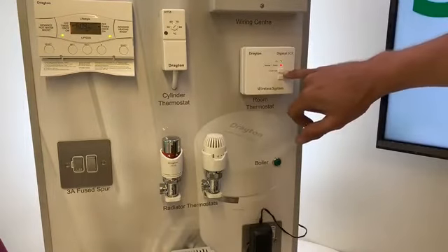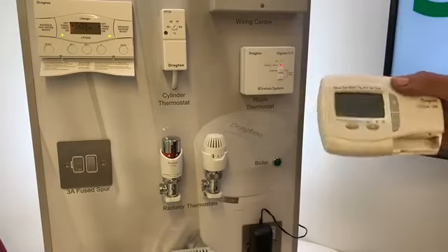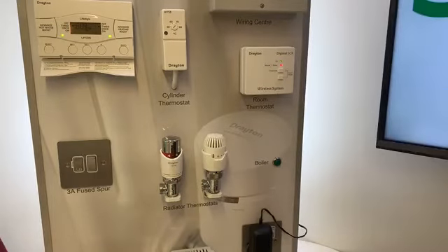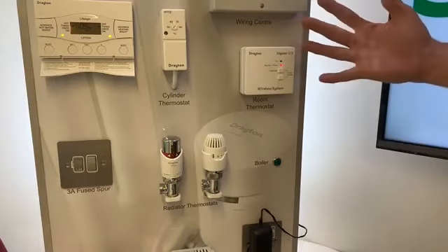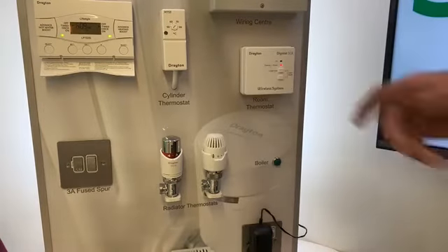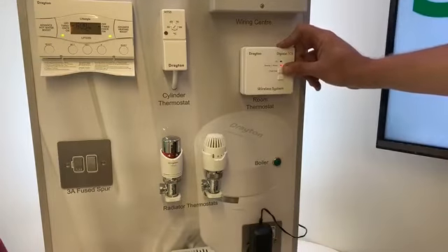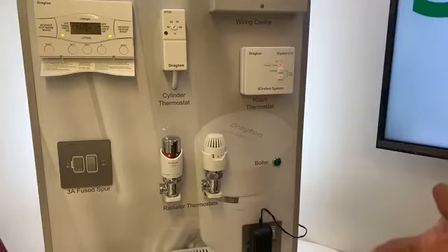Now, this override doesn't work when you've got a control paired to it, because you can't override a working system. The override is designed so that if for some reason this has fallen off of the network, the customer can go in and actually get control of their system. So by hitting the override, that will actually fire the relay and switch whatever it is downstream that you're switching.